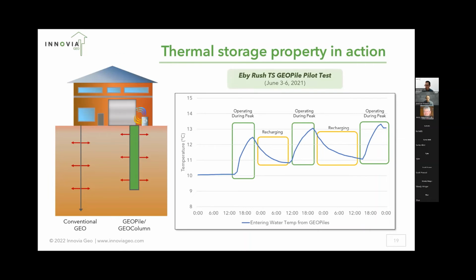And what we can see here is this is the entering water temperature to the heat pump. And so at the moment we shut it off, we see that that temperature is dropping. And so what's happening is that the heat that's accumulated within that fluid, it's still dissipating that heat with the ground naturally because there's a temperature difference that exists. And so we're not having to put an energy input into the system to have that happen. It's just naturally happening because of that pull towards the stable temperature of the ground.